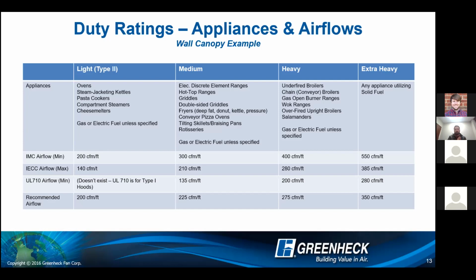So what Greenheck has come up with is our recommended airflow rates. These recommended airflow rates are going to be listed at the bottom here. And this is just based on our experience over time. You're going to see that they're much higher than the UL 710 minimums, but these are what we have found work through our years of experience within the kitchen ventilation system.